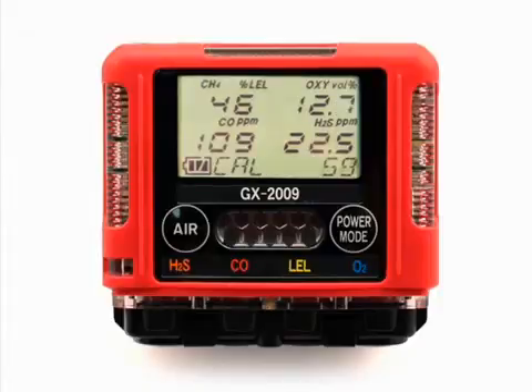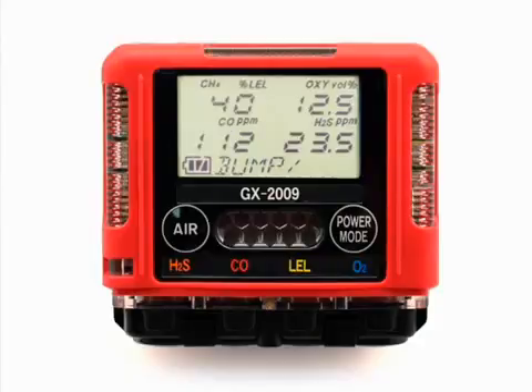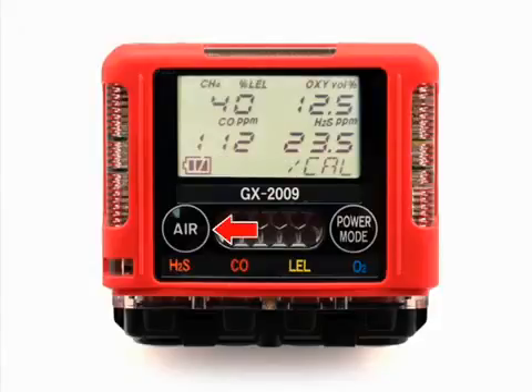When calibration after bump test failed is set to on, and if any channel fails the bump test, the instrument will beep and a calibration is immediately and automatically started. Continue to apply calibration gas. At the end of the calibration, the instrument displays the results from both the bump test and the calibration. To view the bump test gas readings, press the air button. To view the calibration gas readings, press the air button again. To return to the bump screen in calibration mode, press the power mode button at any time. Turn the regulator on-off knob clockwise to close it.